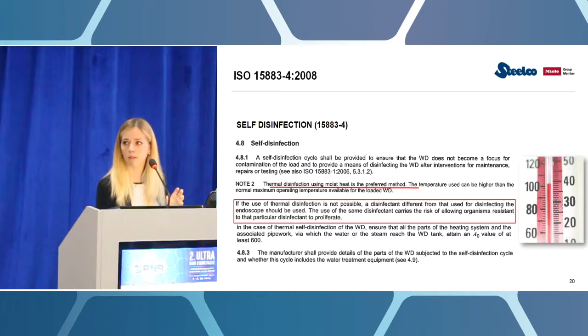Thermal disinfection is the preferred method because you simply heat the water to a very high temperature, around 80 degrees, and keep it there for about 10 minutes, achieving the same result as using a chemical. This is possible with our machines because all the chambers are made of stainless steel, so there's no problem with plastic withstanding high temperatures, since stainless steel can withstand temperatures over 90 degrees. That's for endoscope washers.